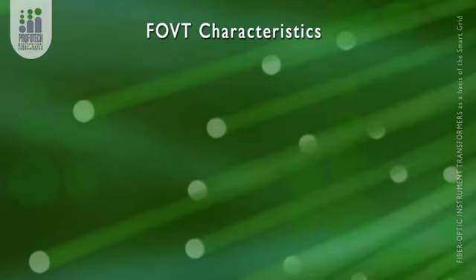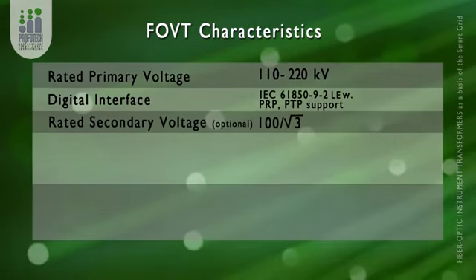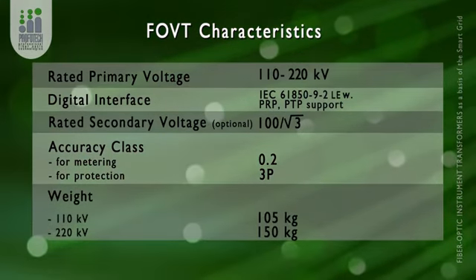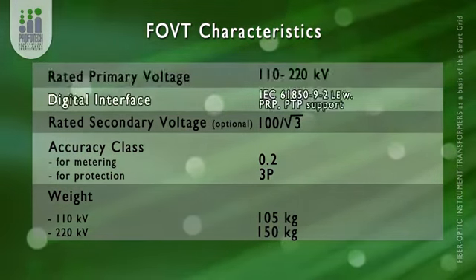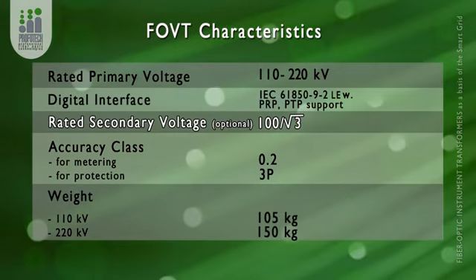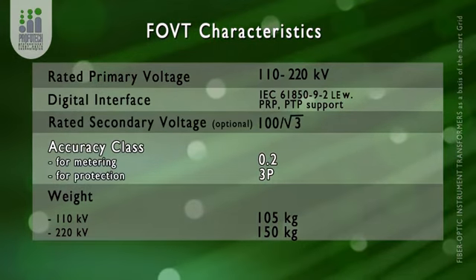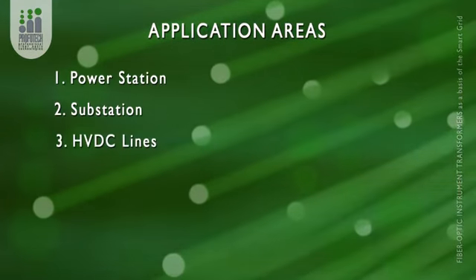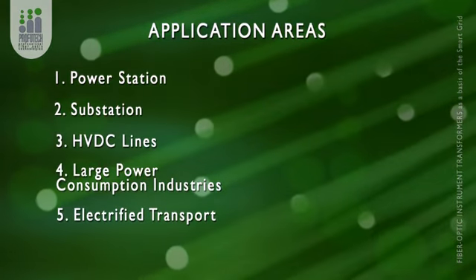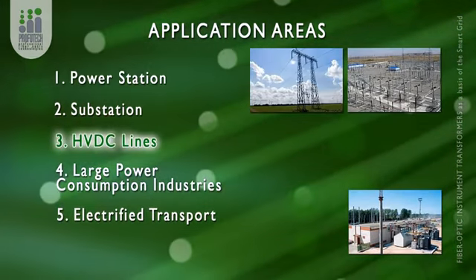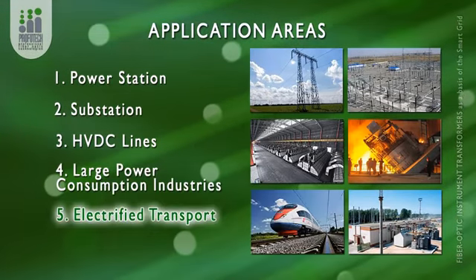This makes it good because we don't have any problems with EMC compatibility. So it is easy to pass any tests and we don't have any problems with high frequencies. Characteristics of the fiber optic voltage sensor are the same, but it is a little bit heavier. The application areas where we need high power consumption are the power energy, power stations, substations, HVDC lines, large power consumption industries, and electrified transport.